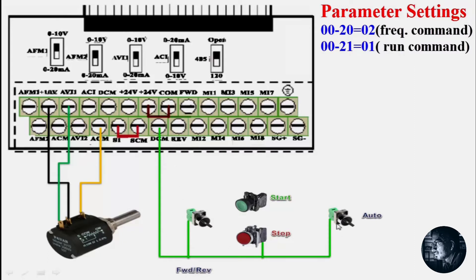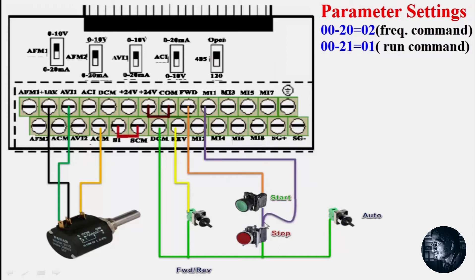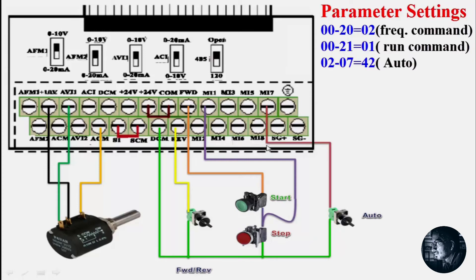The second point from the reverse selector switch is given to the reverse terminal. We connect the second point of the stop button to the first point of the start button. Then from the second point of the start button we connect to the forward terminal. From the common point of the start and stop buttons we connect to MI1, multi-function input 1. The second point of the auto selector switch is given to MI7.